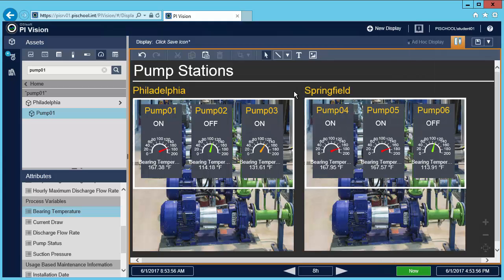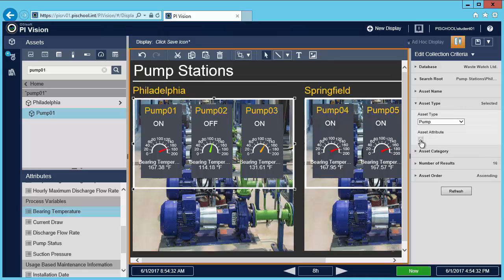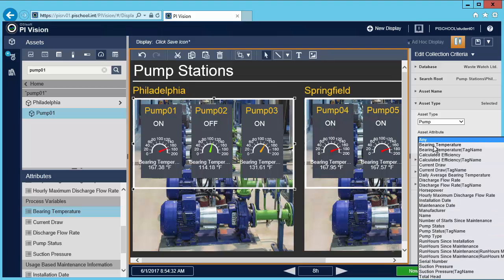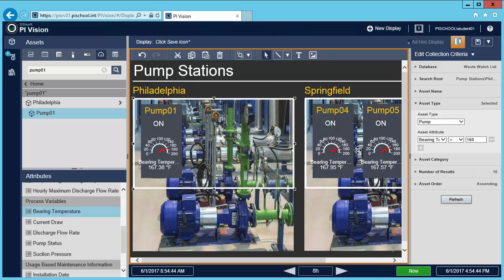The display gives me the situational awareness I need to monitor assets across both sites. But what if I want my collections to show me only the pumps with the out-of-spec temperature? To do that I'll need to change the collection criteria again. I'll right-click and then under asset type I'm going to choose the asset attribute which is bearing temperature, change the operator to greater than 160, which is my threshold temperature.